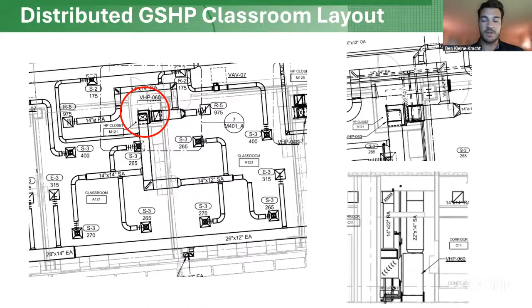Do they generate much noise, Ken? I'm just wondering about the noise level with these pumps. Yeah, that's a good question. They make these so specialized now that they have highly acoustically rated cabinets. They have sound blankets for the compressors themselves. We always spec the first 10 feet of return and supply ductwork to be internally lined. It is a valid concern, and we're always going back and forth with the acoustic engineer to make sure everything is taken care of. But I think they're really quiet. I haven't had anyone tell me they were loud. But they make a lot of accessories we could explore to decrease that sound further.